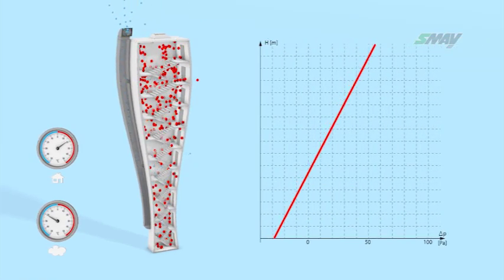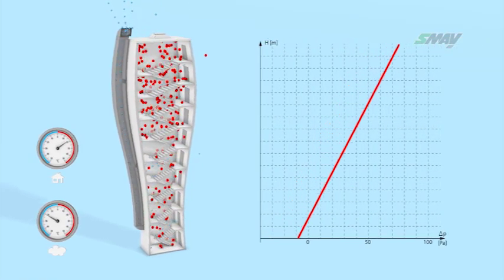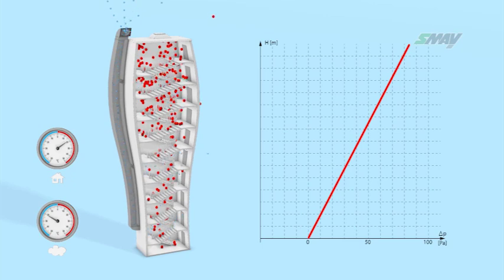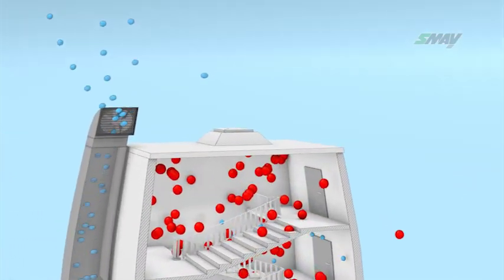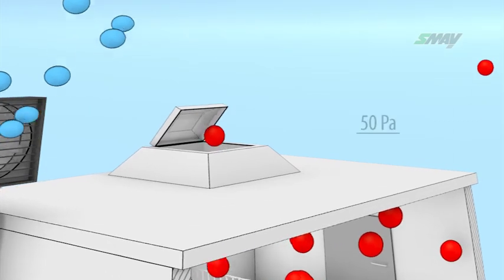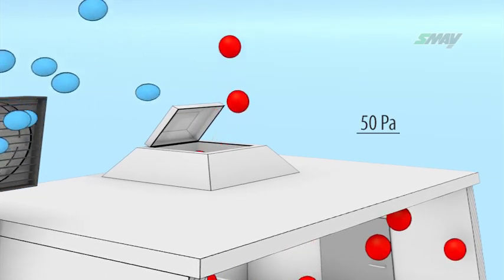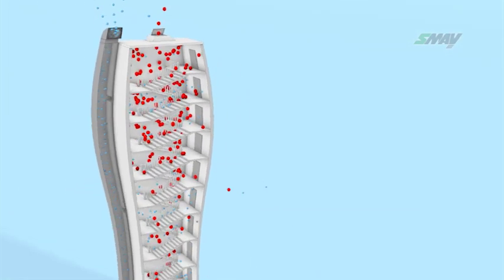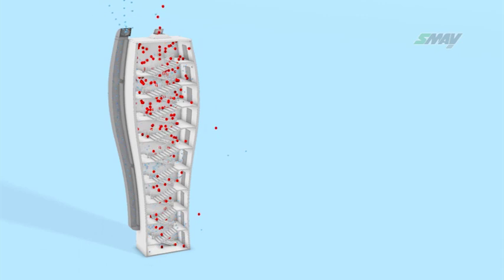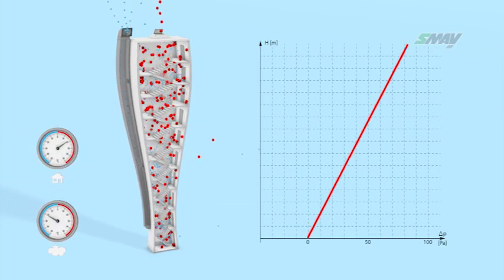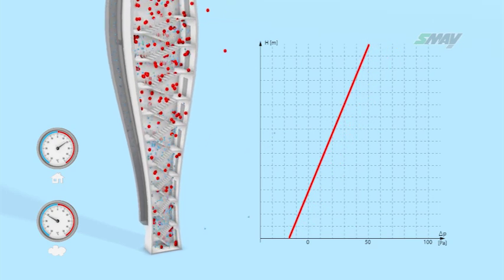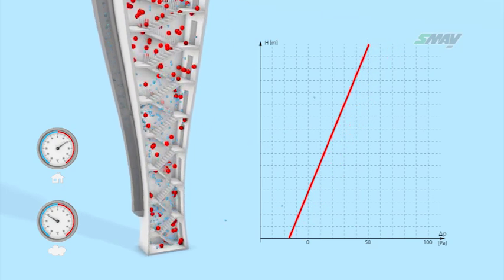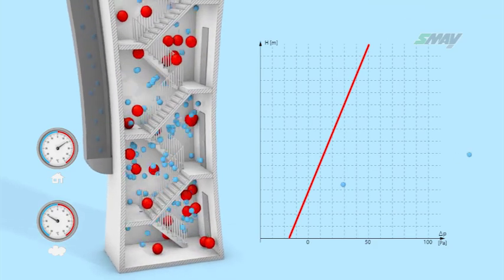Consequently, air pressure rises in the upper parts of the stairwell. The excessive pressure rise in the upper parts causes the barometric overpressure dampers to open, doing their job of maintaining pressure at no more than 50 pascal. The cut-off dampers only restrict pressure locally in the upper parts of the stairwell. Overpressure in the remaining parts is not controlled in any way and may fall below the required minimum.